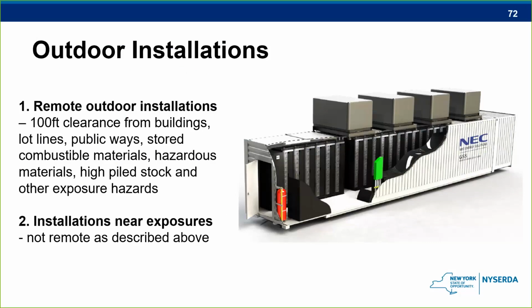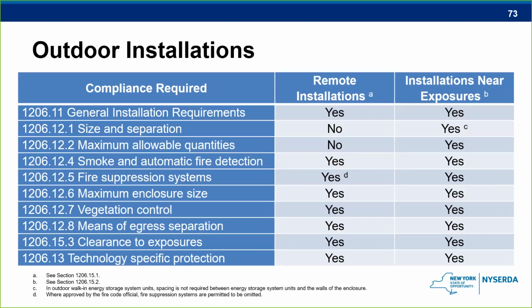So now moving on to outdoor installations specifically, like I said before, they're either defined as being remote or near exposures. A remote outdoor installation would have at least 100-foot clearance from buildings, lot lines, public ways, anything that it could potentially damage if an incident were to occur. And installations near exposures are less than 100 feet away, not remote, as described above. So, of course, remote systems will not have the same requirements as other outdoor systems, again, because they don't pose the same life safety risk factor involved, so their requirements are less stringent.